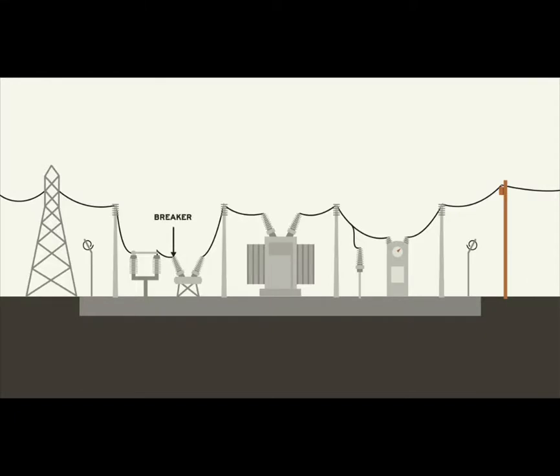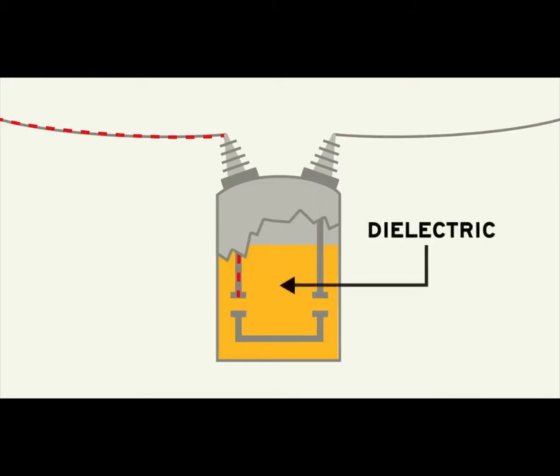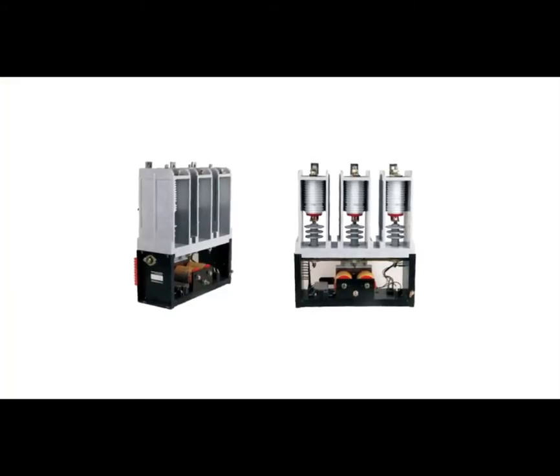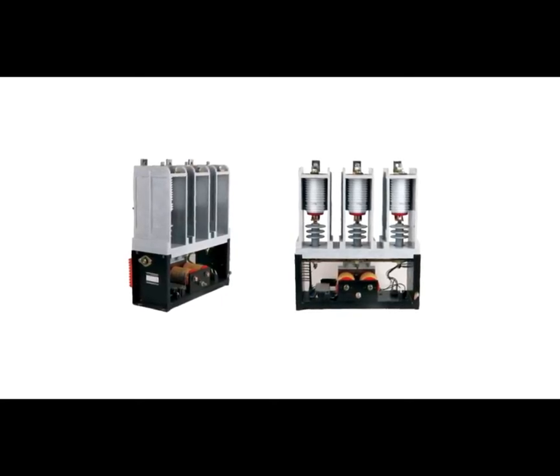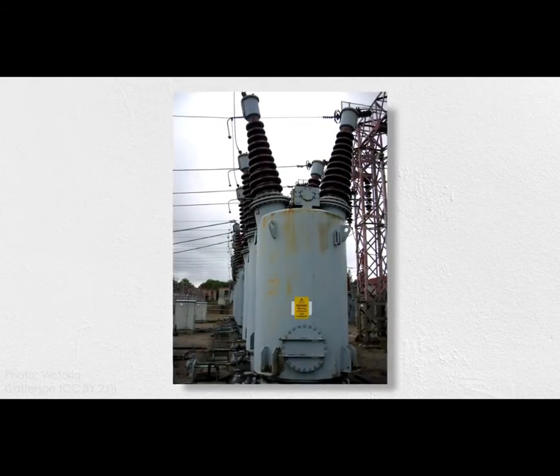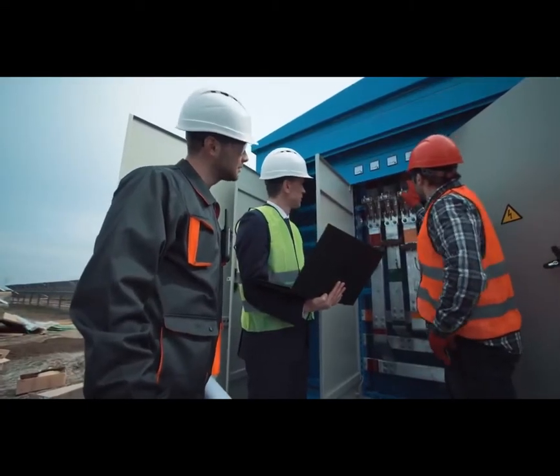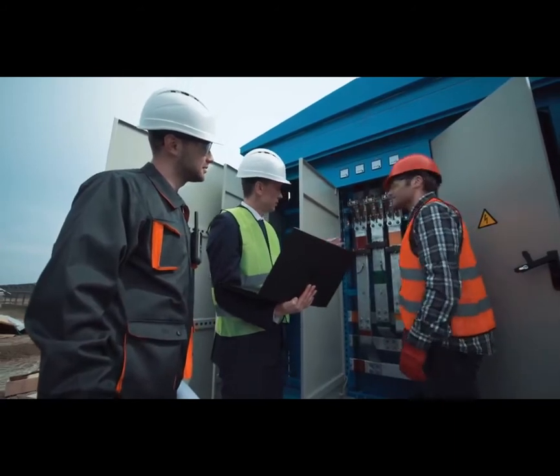Circuit breakers are a class of devices that serve similar roles as fuses but provide more sophistication for dealing with a wide variety of faults. Like disconnect switches, circuit breakers need to be carefully designed to interrupt huge voltages and currents without damage. As soon as contacts within a circuit breaker are moved apart, an electrical arc forms, which needs to be extinguished as quickly as possible. This is accomplished by a dielectric material that doesn't conduct electricity. For lower voltages, breakers can be in a sealed container under vacuum; for higher voltage, breakers are often submerged in tanks filled with non-conductive oil or dense dielectric gas. These breakers give grid operators more control, and sometimes operators even know about a disturbance ahead of time and can trigger breakers early to prevent cascading failures.